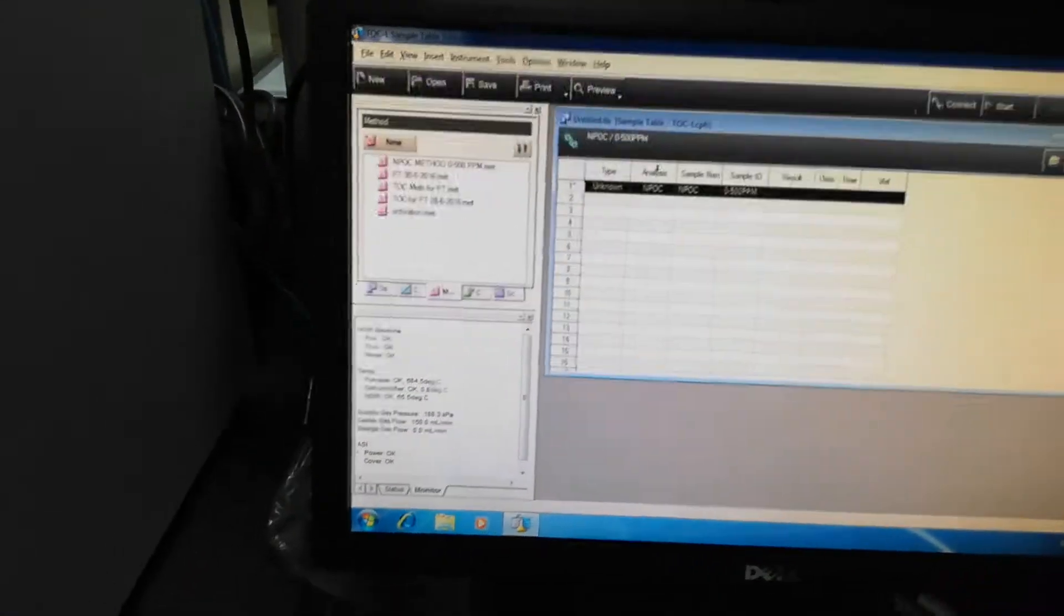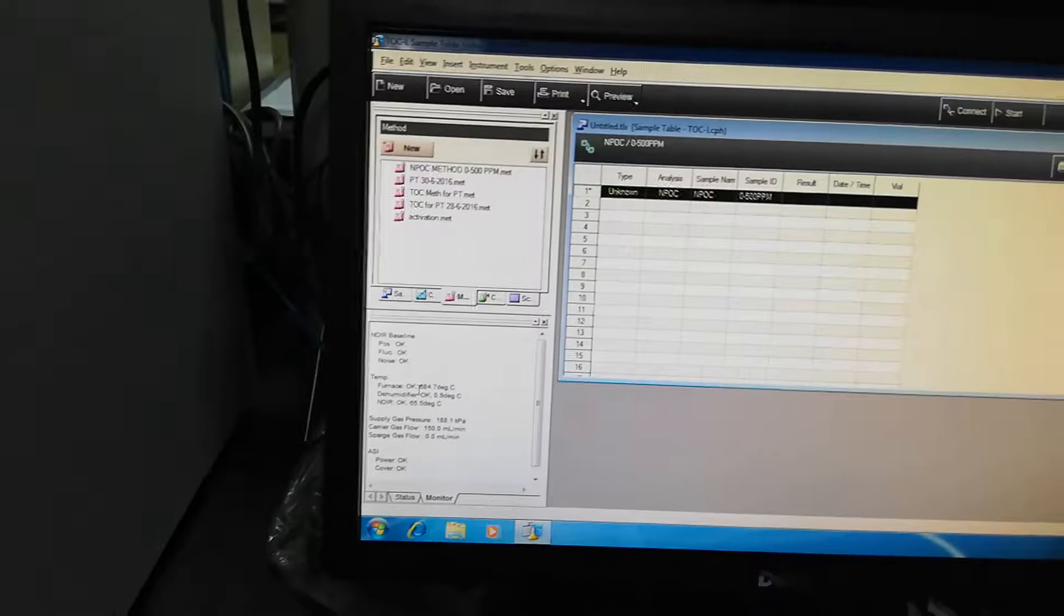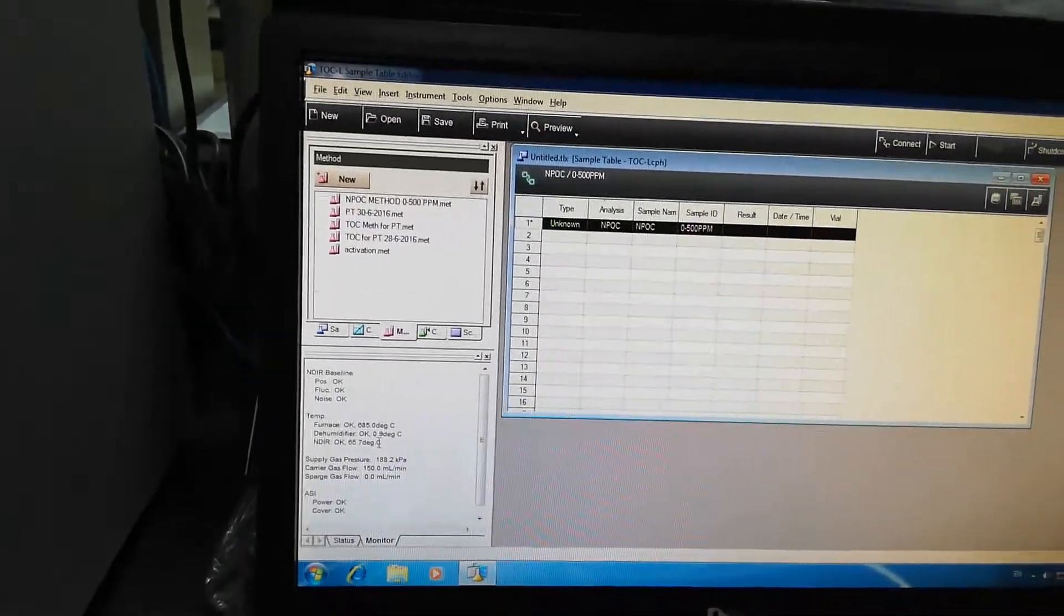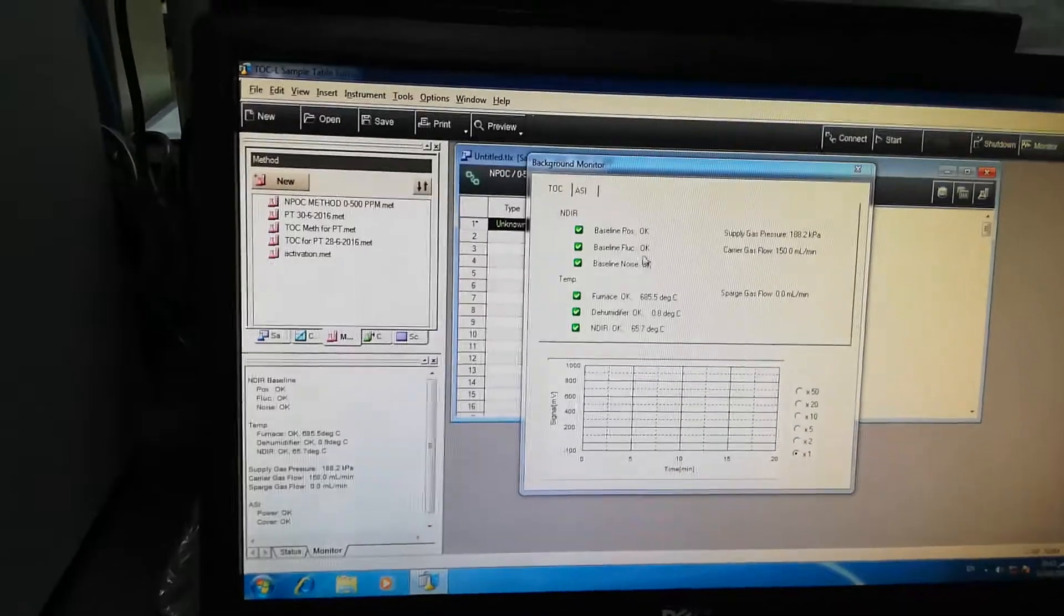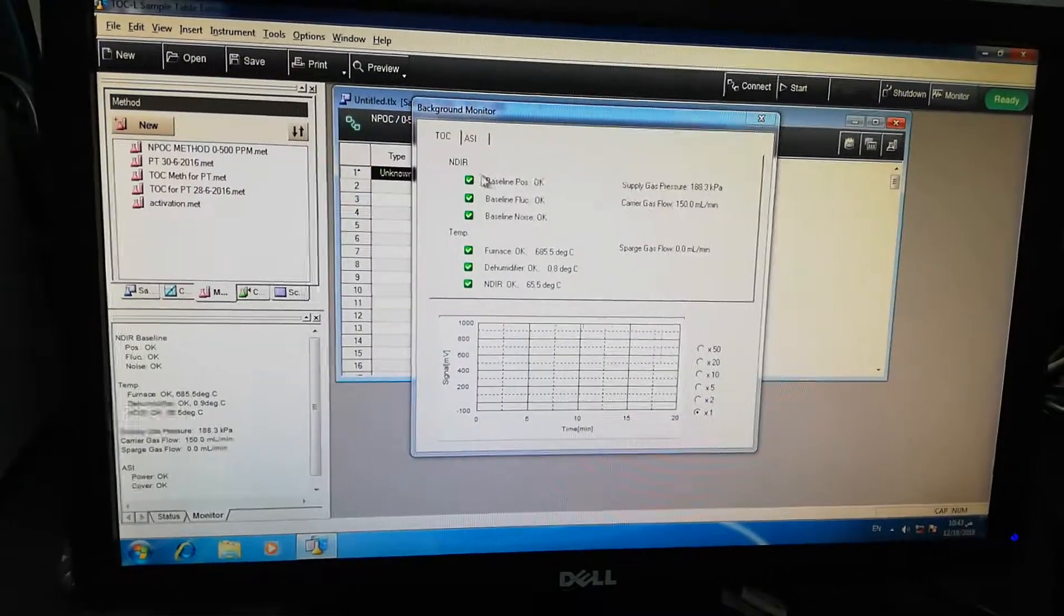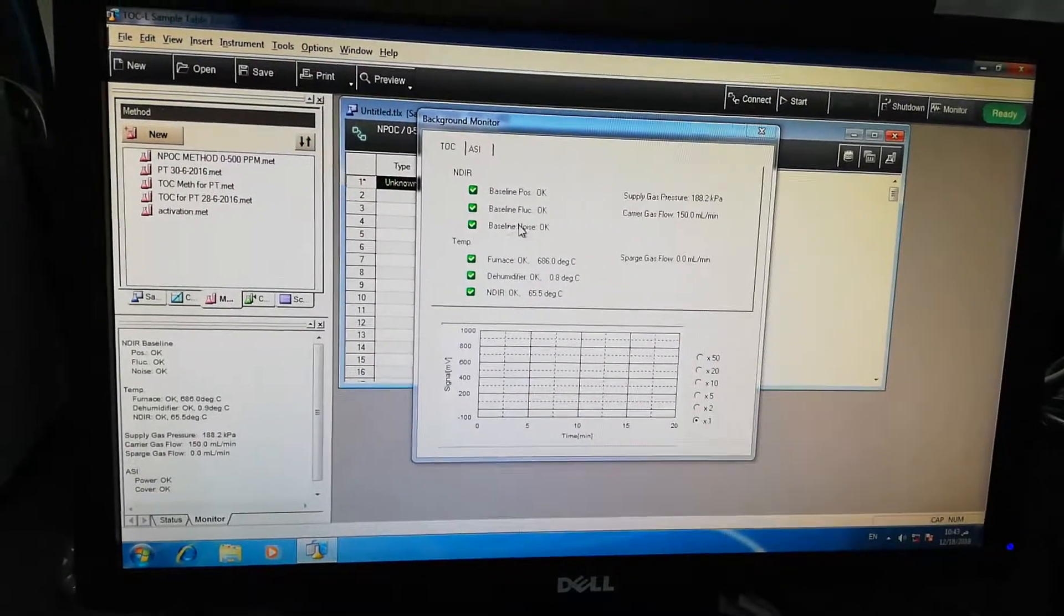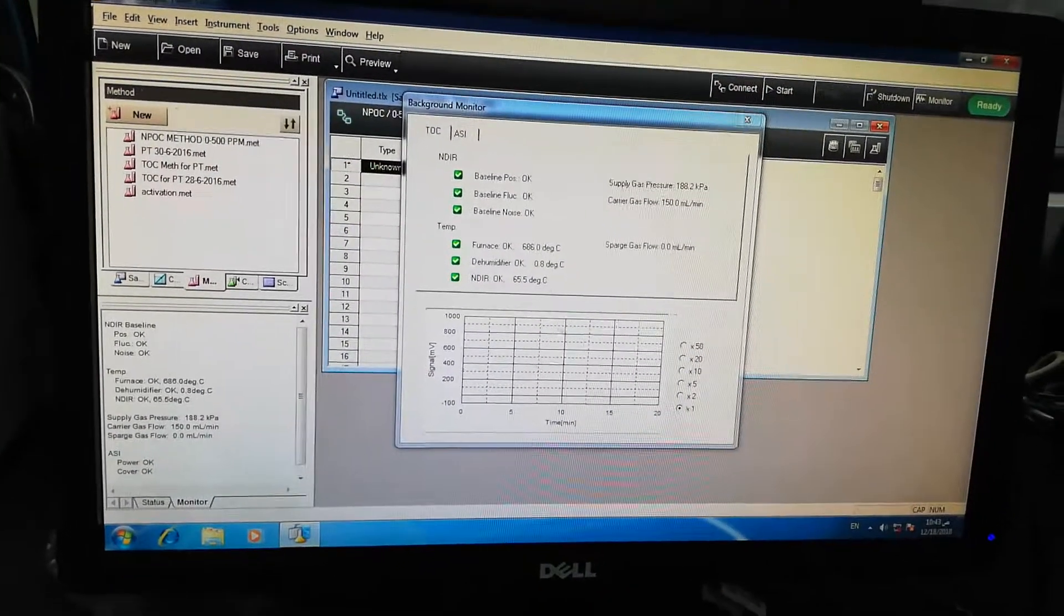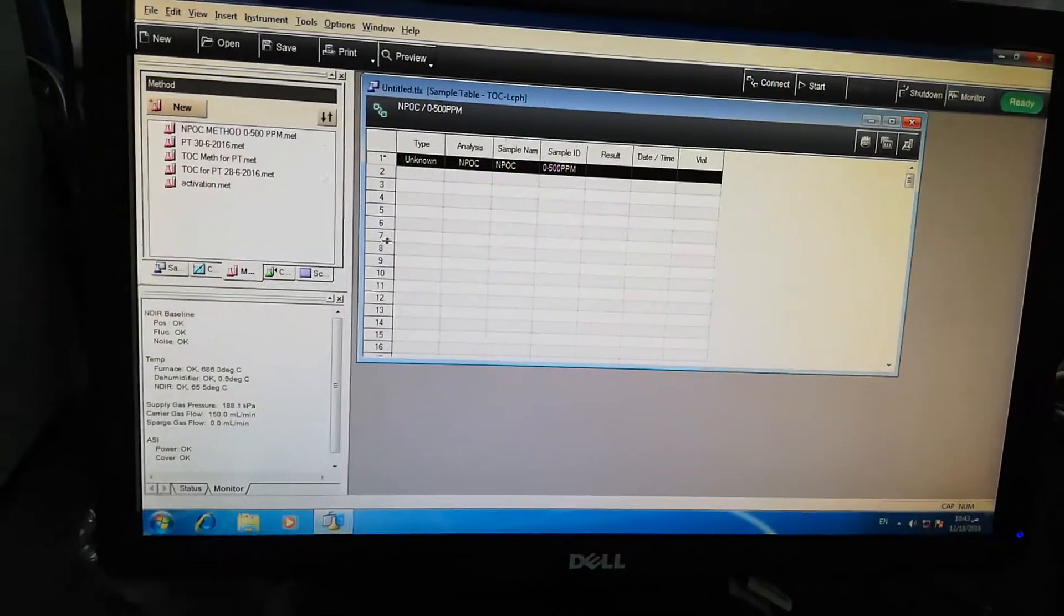Bismillahirrahmanirrahim, now we will start it again. You can see now the furnace temperature is almost okay, all the other parameters okay. Monitor, you can see all the NDIR baseline, baseline position, baseline fluctuation, furnace temperature - all are okay. So now what we will do...